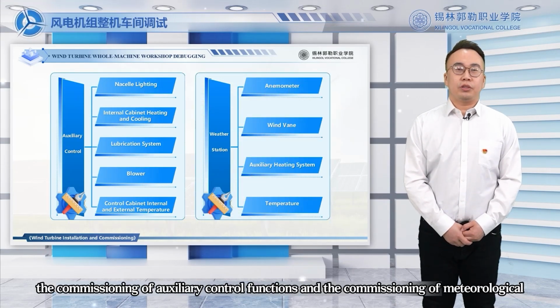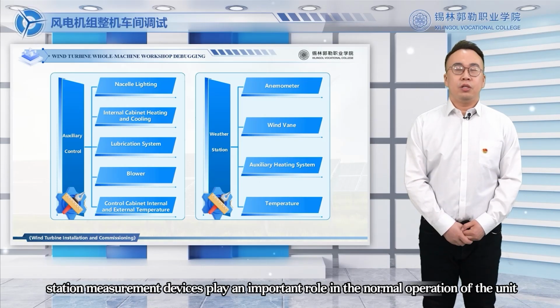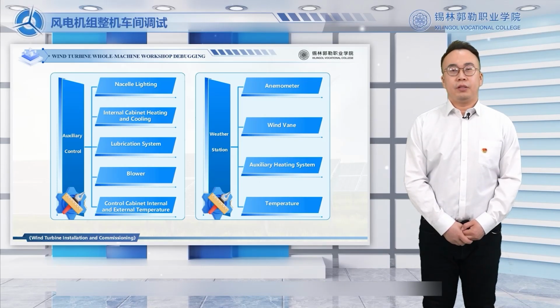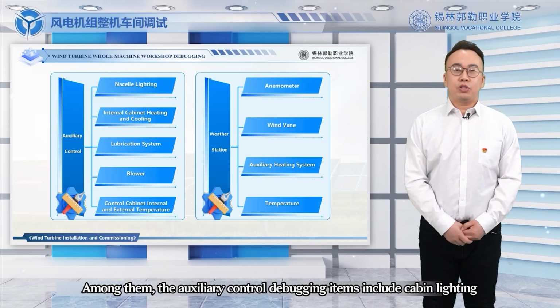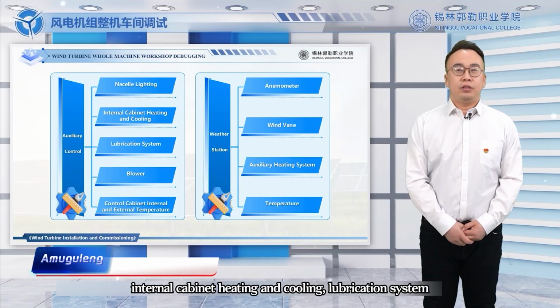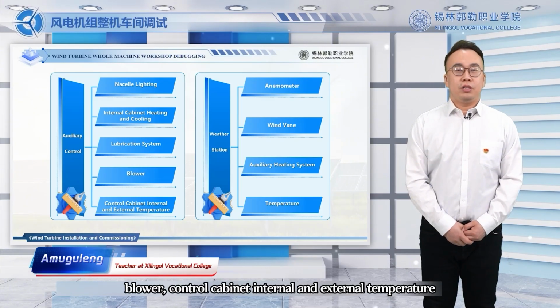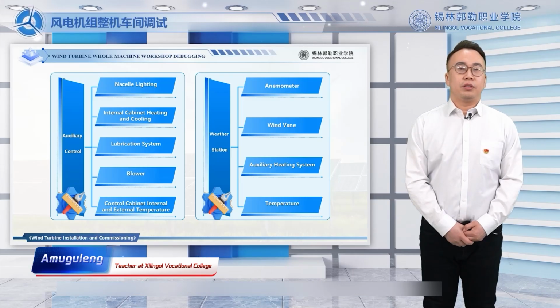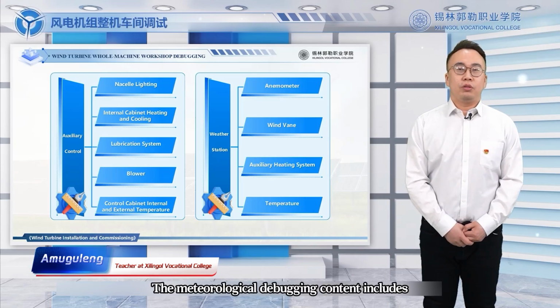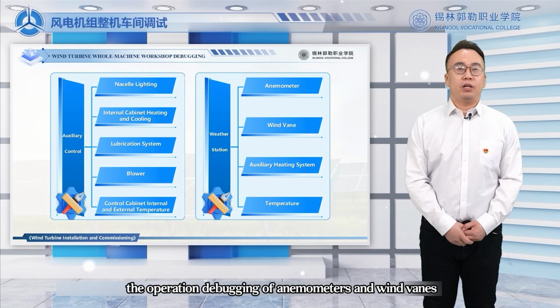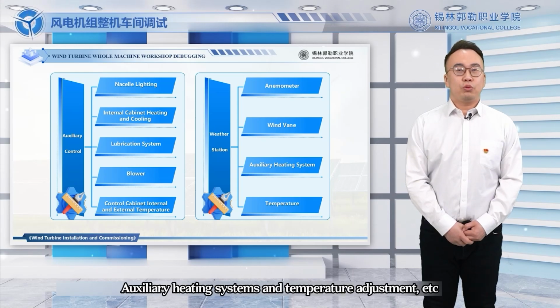During cabin commissioning, the commissioning of auxiliary control functions and meteorological station measurement devices play an important role in the normal operation of the unit. Auxiliary control debugging items include cabin lighting, internal cabinet heating and cooling, lubrication system, blower, and control cabinet internal and external temperature. Meteorological debugging content includes operation debugging of anemometers and wind vanes, auxiliary heating systems and temperature adjustment, etc.